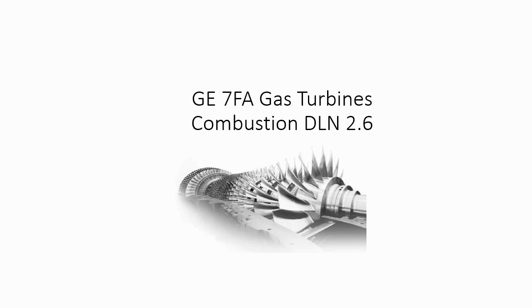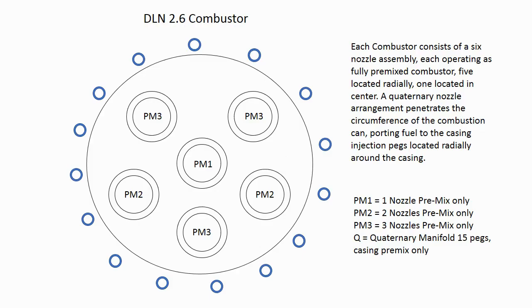DLN 2.6 combustor. Each combustor consists of a six nozzle assembly, each operating as a fully premixed combustor, five located radially and one located in the center. The quaternary nozzle arrangement penetrates the circumference of the combustion can, porting fuel to the casing injection pegs located radially around the casing.